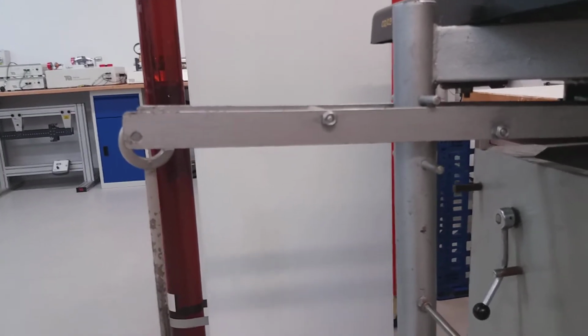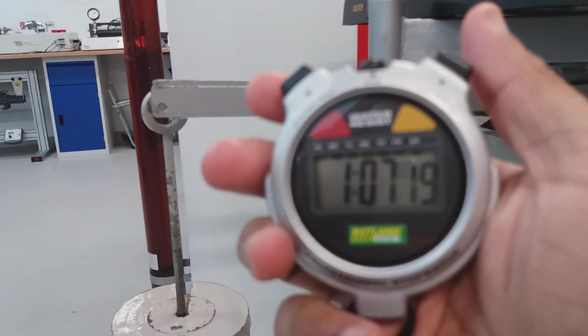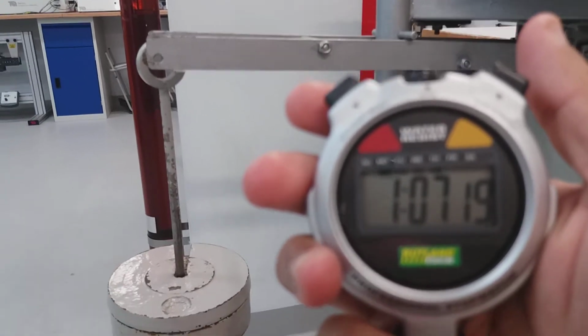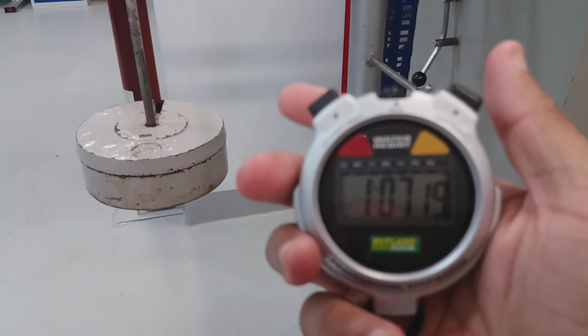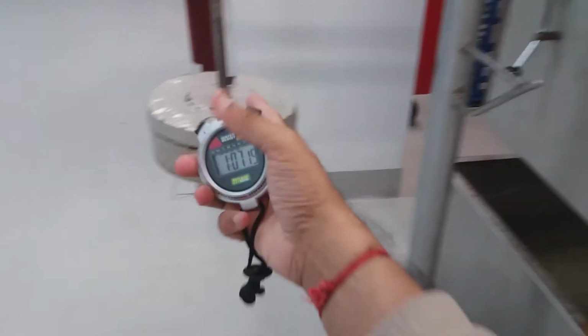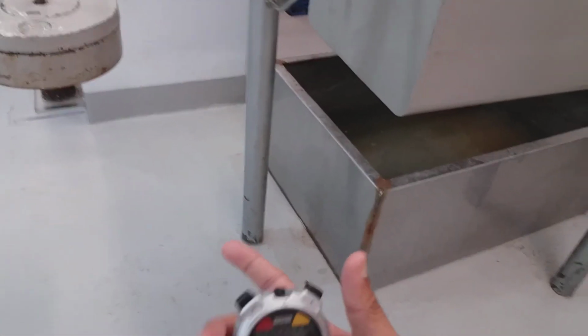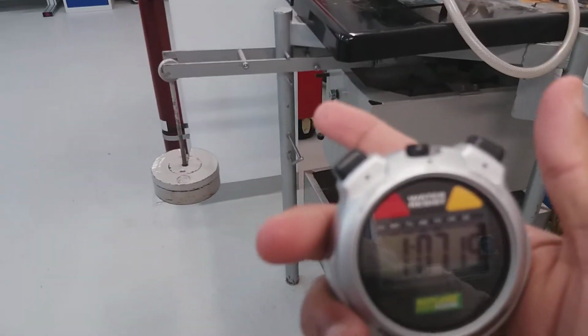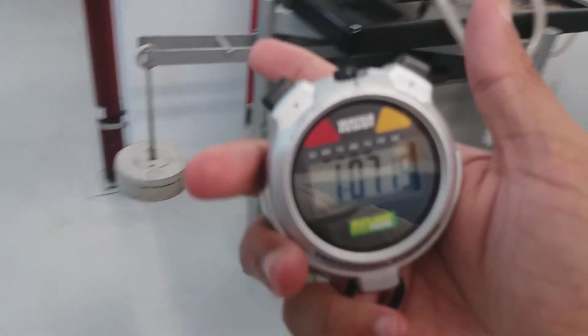So you can see that the lever is slowly tipping over, and then it's tipped. So basically I've stopped the clock and noted the time it has taken to collect the mass of water that corresponds to the second weight that we've put in. The first weight is just a counterbalance weight. It doesn't tell you anything. The second weight is the weight that tells you how long it has taken for 15 kilograms of mass, the equivalent of mass being collected by the tank in the form of water.